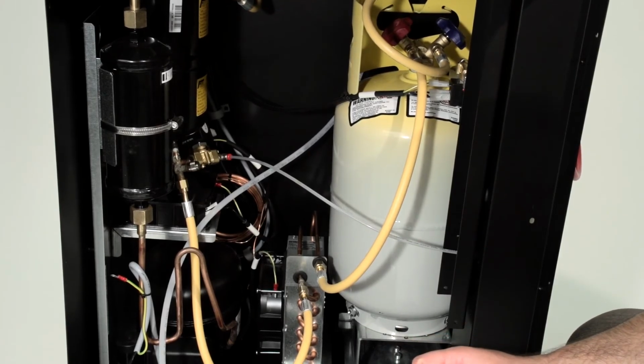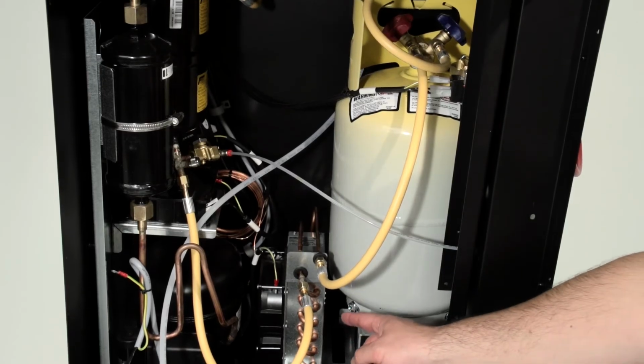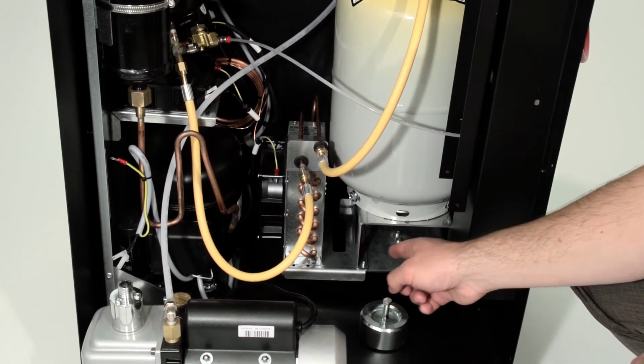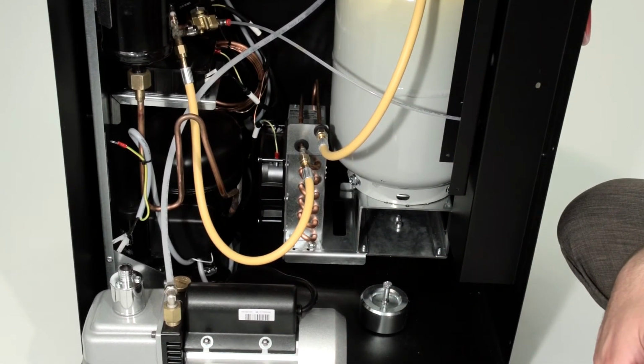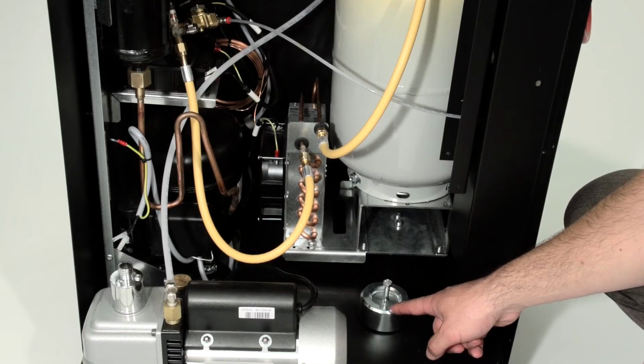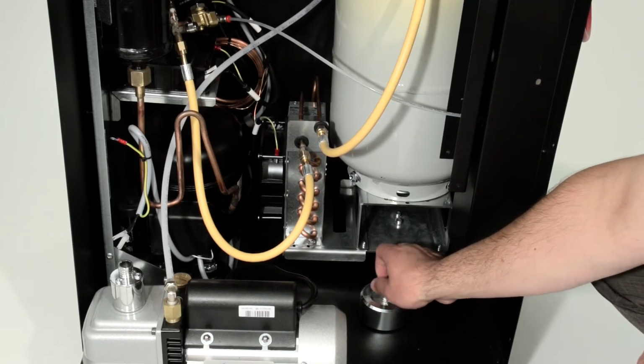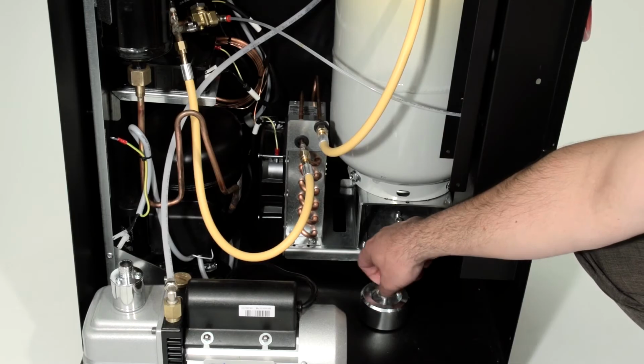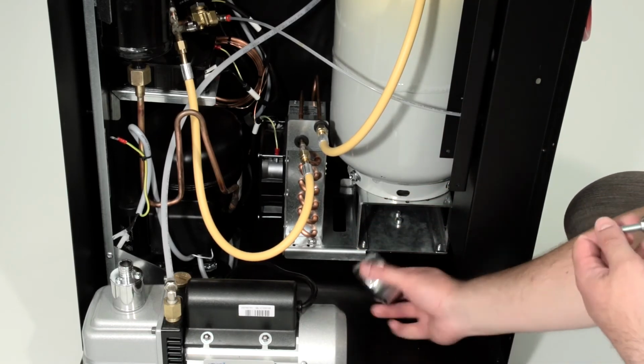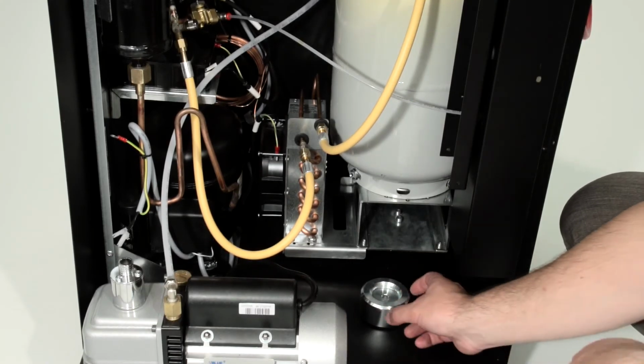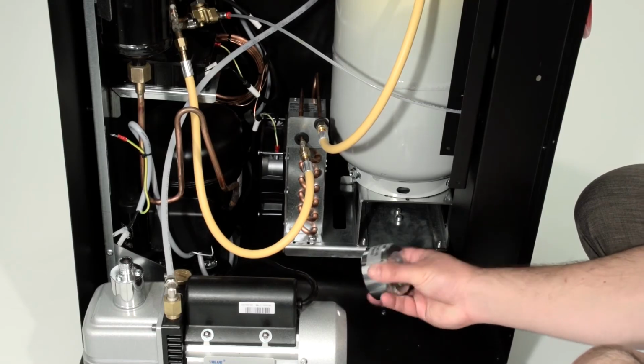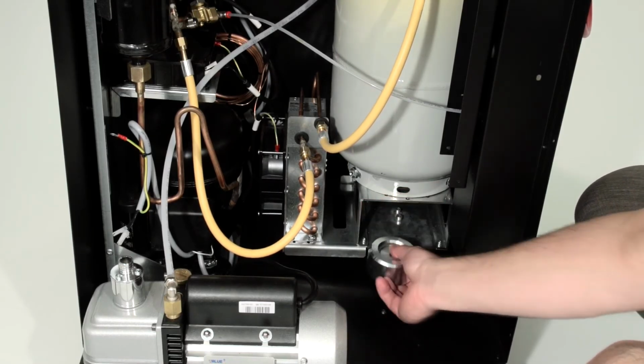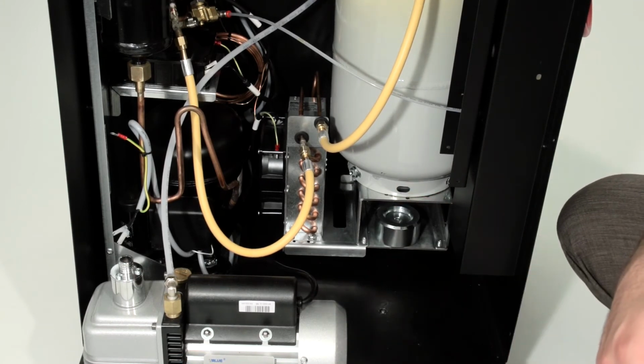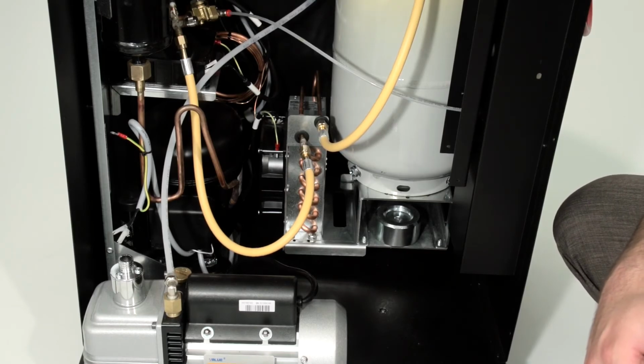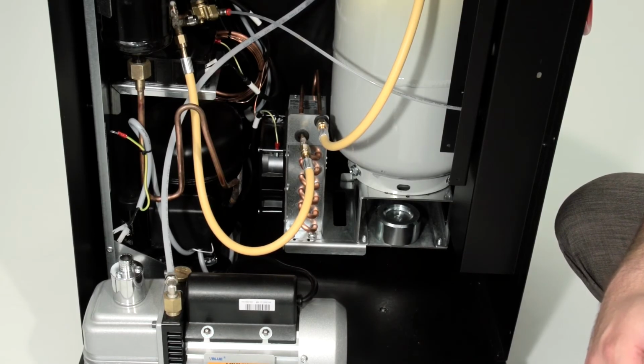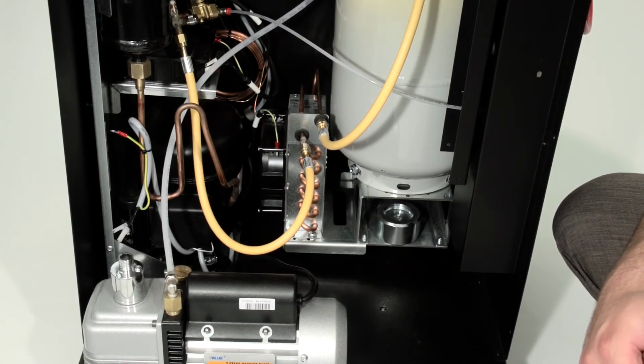The 1120H, 1150, and 1150H have this condenser with a fan here that is also on our load cell. This weight down here in the bottom, this is our calibration check weight, which is just secured by this bolt and wing nut. If we were doing a calibration check, it has the amount printed on it, and we just set it inside here, and we verify on the screen that the weight increases by that amount. That would be the calibration check for 1120H, 1150, and 1150H.